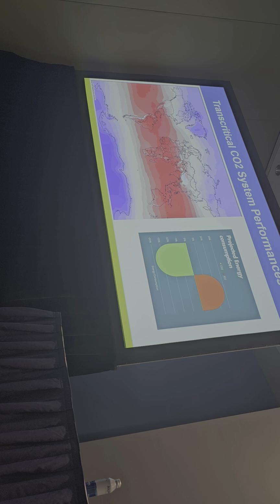Now if I come back next graphic on the right, remember what we were projecting on the energy simulation? We were thinking that we're going to get 19% reduction versus the existing system. If you keep thinking about it, when we are under a CO2 transcritical mode, remember when I said that when we are in transcritical, we are no longer condensing? So we're going from a very warm gas and we're cooling it down. So it also changed the dynamic in terms of heat reclaim. We have discharge temperature sometimes close to 300 degrees Fahrenheit. And we keep going down, down, down, and as low as possible.